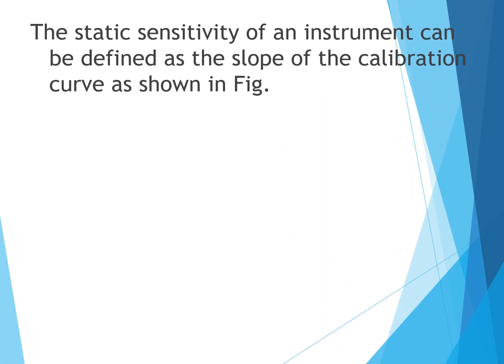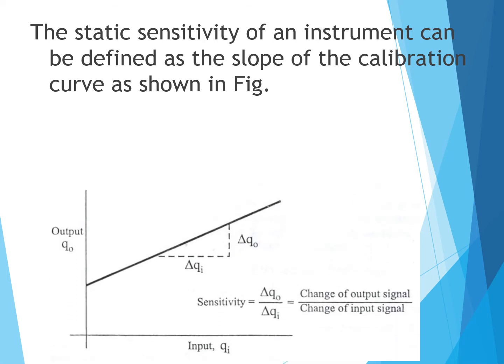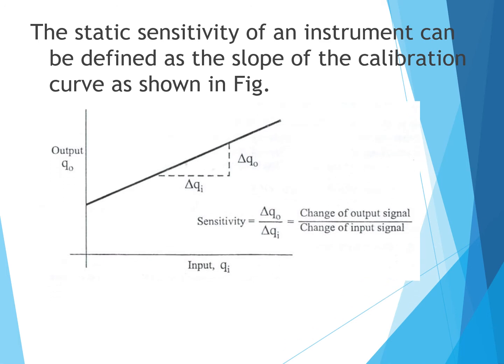The static sensitivity of an instrument can be defined as the slope of the calibration curve. If I plot output versus input on a graph, for a given input I get a corresponding output. When I plot this curve, the change in the y-axis reading divided by the change in the x-axis reading gives me the sensitivity — that is, change in output signal divided by change in input signal, or (y2 - y1) / (x2 - x1).